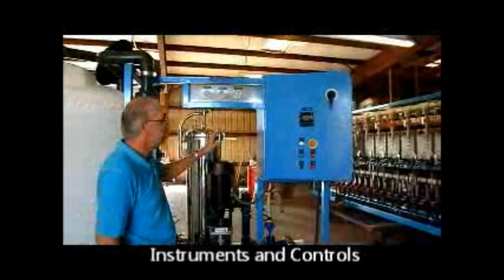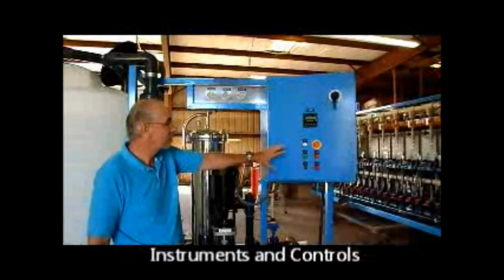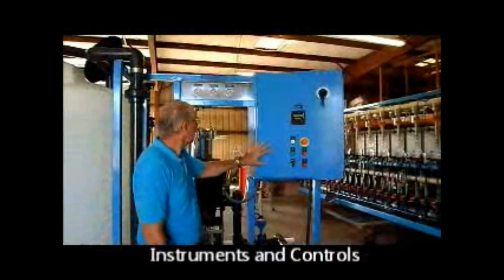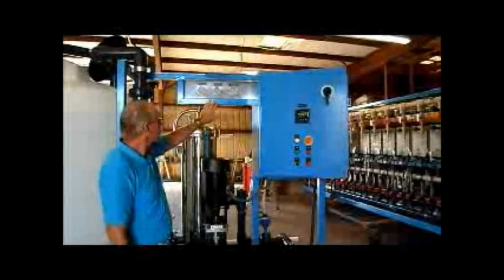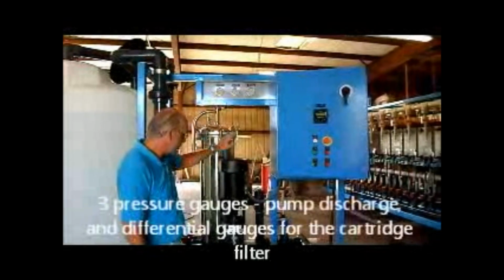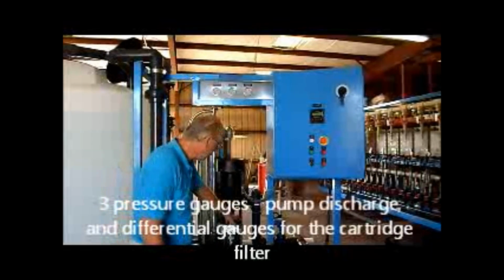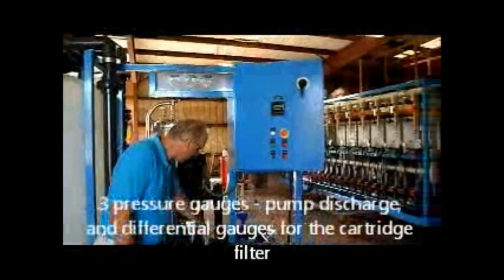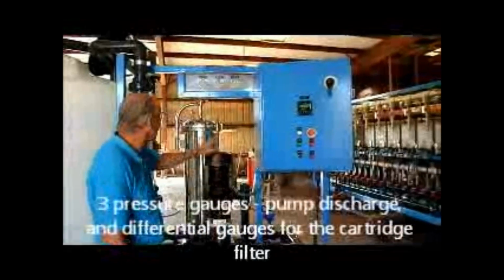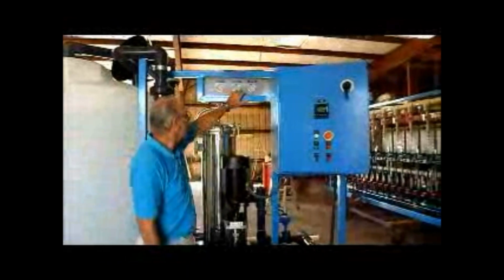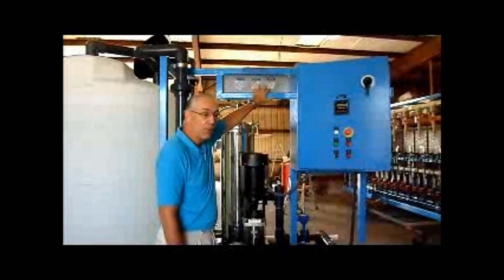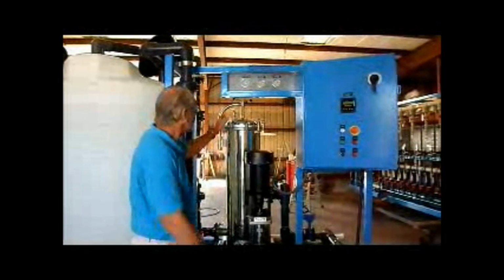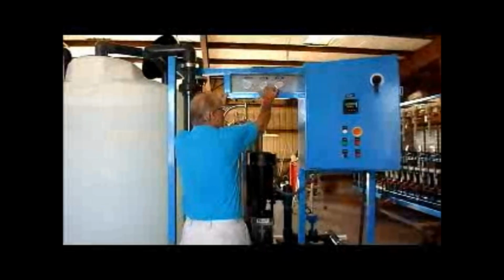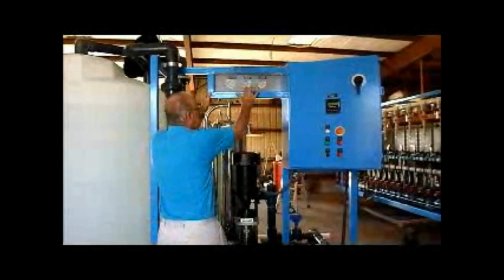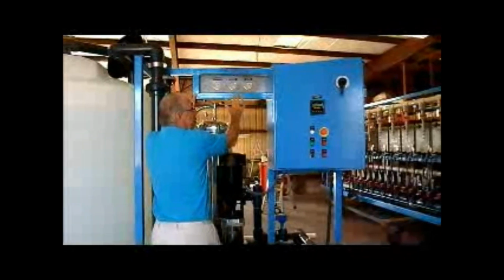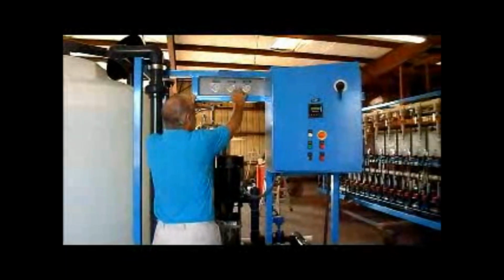Let me explain now the instruments and controls of the system. We have 3 pressure gauges. The first one measures the pump pressure coming out of the discharge of the pump before this valve, the other valve just coming out of the pump. Then we have 2 that are before and after the cartridge filter. These 2 you should examine, check the differential pressure across the 2 gauges. Start as normal.